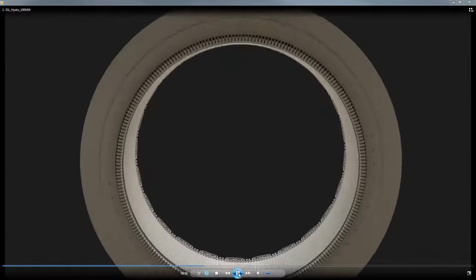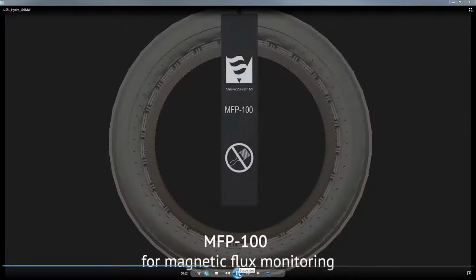Okay, an example of a sensor installed here. And then in some cases, if you want to measure the situation in regards to excitation provided by the rotor, the magnetic flux which is generated by each pole, there's a magnetic flux probe that is also installed on the core next to an air gap sensor, and that is used to see if there are any shorted turn issues on any or many of the poles of your rotor.